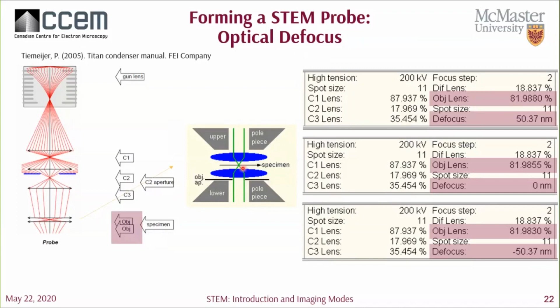As we increase the objective lens, we're placing the crossover point at a position that's above our specimen, or our arrow, while decreasing our lens will position your crossover point below the specimen. Just a note, adding a little bit of defocus can help compensate for the phase shift in the probe due to spherical aberrations. And this leads us into the discussion of aberration correctors.